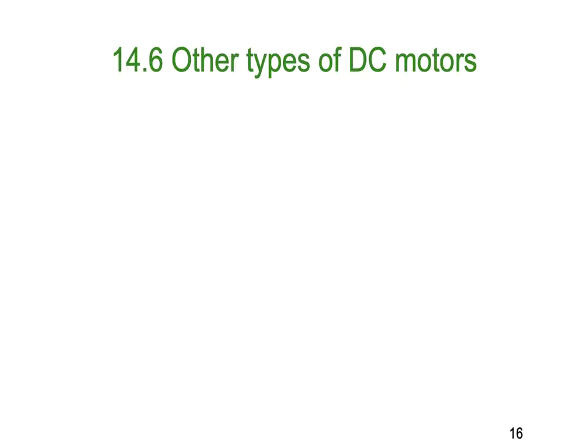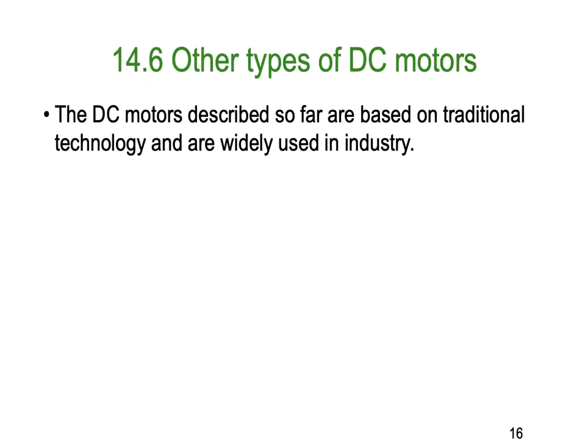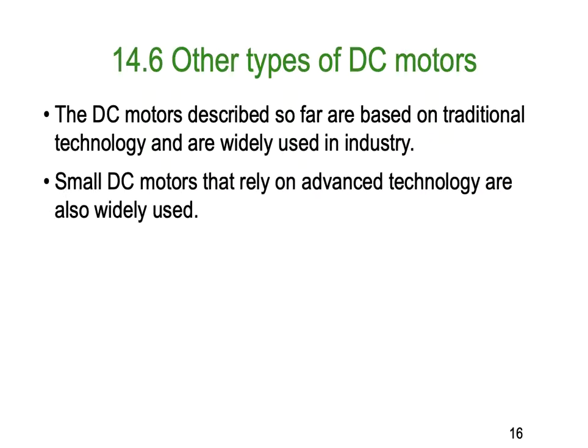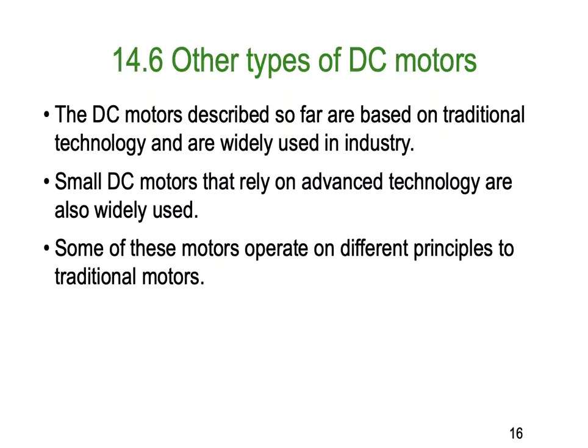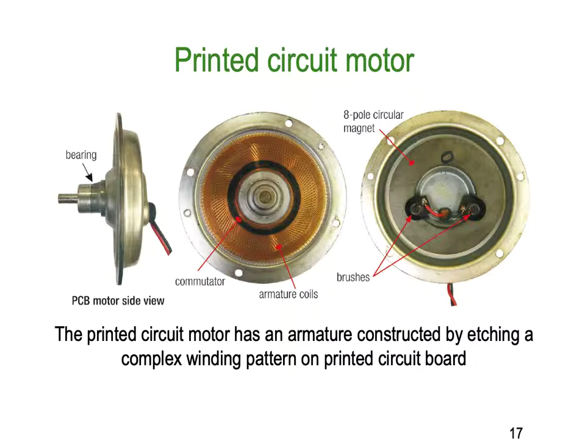DC motors described so far have been based on traditional technologies that have been widely used in industry for 200 years now. Small DC motors that rely on advanced technology are also becoming very widely used. Some of these motors operate on different principles than the traditional motors. Here's a printed circuit board motor — the actual windings are part of a printed circuit board. It's a very flat motor. The armature is constructed by etching a complex winding pattern onto a printed circuit board, and you can see it here. There is still a traditional commutator, but the commutator itself is also printed onto the circuit board.